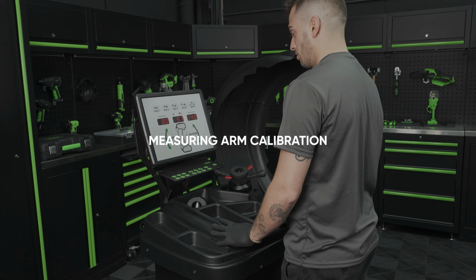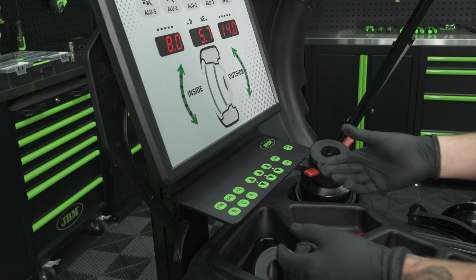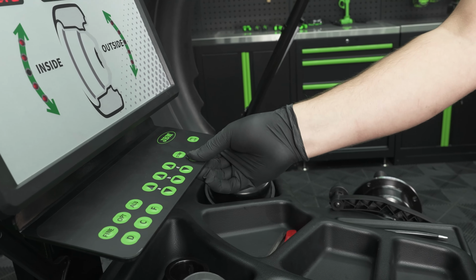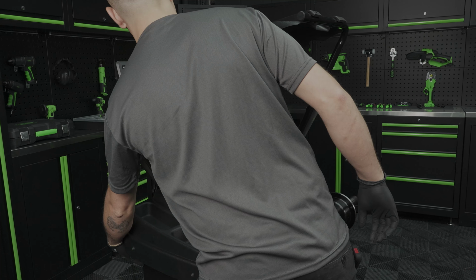To start the process, press and hold the stop and fine keys. Then, press the stop key. With the scale in the 0 position, press the ALU key to confirm. Move the scale to position 15 and press the ALU key again. Once this step is complete, the measuring arm calibration is finished.